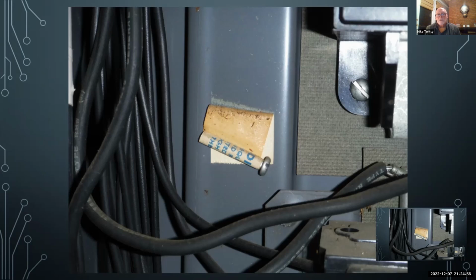If you're going to use it as a sub panel or a service panel, then it's up to you whether you put the bonding screw in to bond the neutral bus. This one was never bonded in all those years. It's still hanging on the wall of that panel. Well, it's not now because this was a home inspection I did, and I had it bonded. But that had been there since 1969.